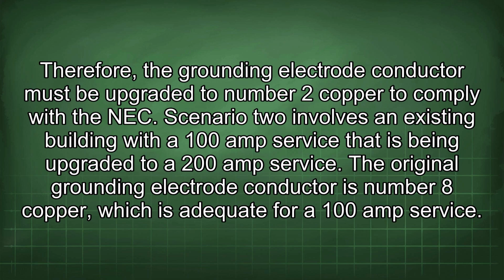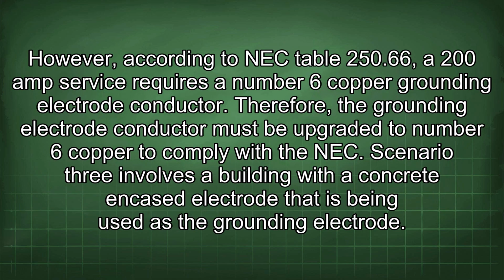Scenario 2 involves an existing building with a 100 amp service that is being upgraded to a 200 amp service. The original grounding electrode conductor is number 8 copper, which is adequate for a 100 amp service. However, according to NEC table 250.66, a 200 amp service requires a number 6 copper grounding electrode conductor. Therefore, the grounding electrode conductor must be upgraded to number 6 copper to comply with the NEC.